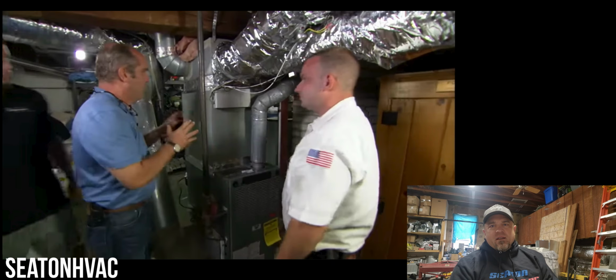Good. So a couple things they could have done while they had this all taken apart. Obviously, they should have done something with the secondary drain. They should have put a safety on it, so if that primary clogs up or if the pump fails, they don't flood out the system, especially with the furnace sitting underneath that coil. You need to have some protection there. And then there should be a 24-volt safety in that condensate pump. So if it fails, it's not going to overflow the pump and flood out the basement, because I see there are doors and stuff there that are low. They probably have stuff sitting on the ground they don't want to get wet, and they could come home to a flooded basement at some point, or at least a good stream of water. So just a couple things I noticed.